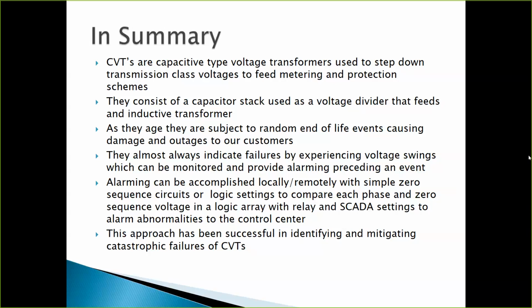We have 14 more minutes. We can answer a few more questions. There's a question from the audience. I'll read out the question for you. Some of the relays use a built-in capacitive voltage transformer supervision element, also provided to detect a voltage error due to a capacitor short-circuited in a CVT. The relay detects a permanent small zero sequence voltage and gives an alarm, adjustable timer. Can this be used for the same purpose?